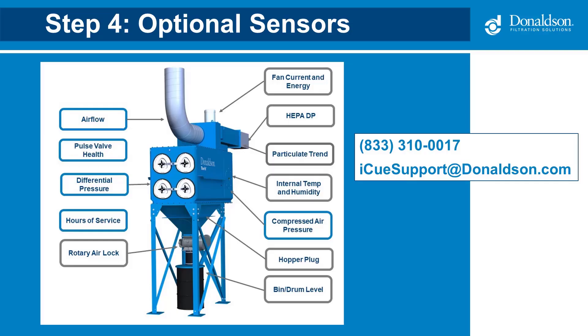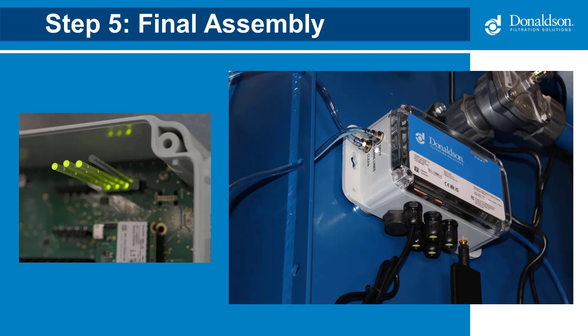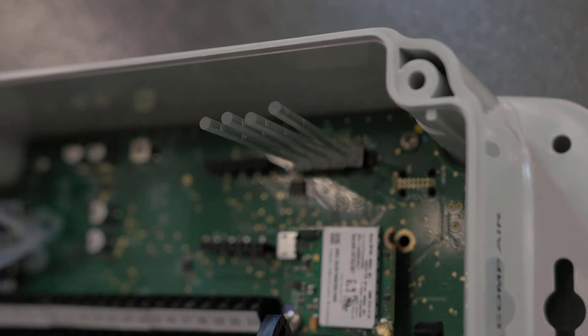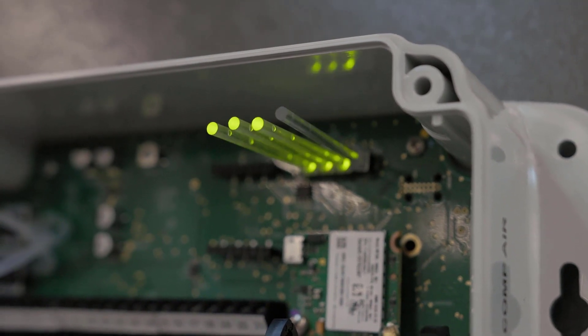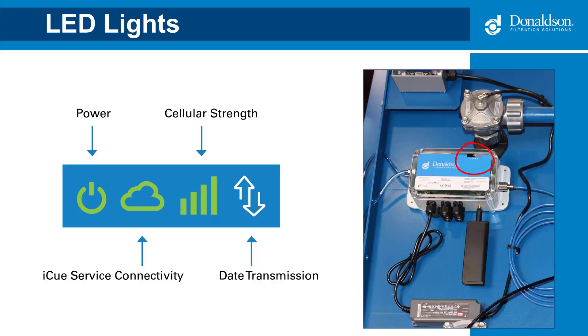Next, install any optional sensors, such as rotary airlock or bin level. If you need help installing them, make sure to contact us. For final assembly, connect the cellular antenna and hand tighten, then restore power. Once the gateway is energized, it will start its startup routine — the lights will go from red to orange to green, which may take several minutes. The gateway is properly connected to the iCue cloud if the power, iCue service connectivity, and cellular strength LEDs are green. The data transmission LED may blink periodically as data is transferred.